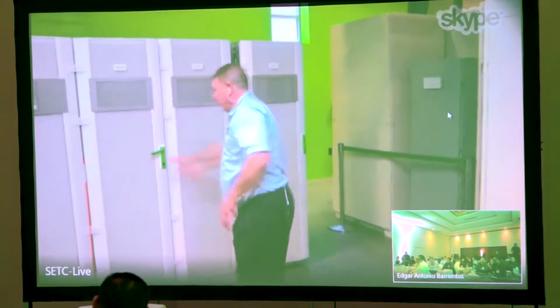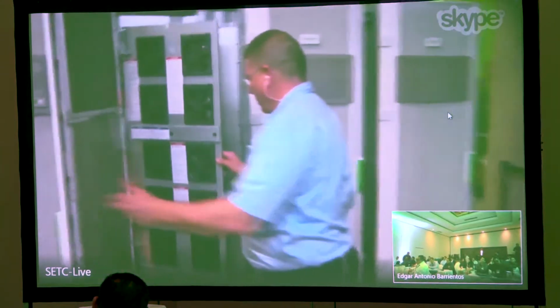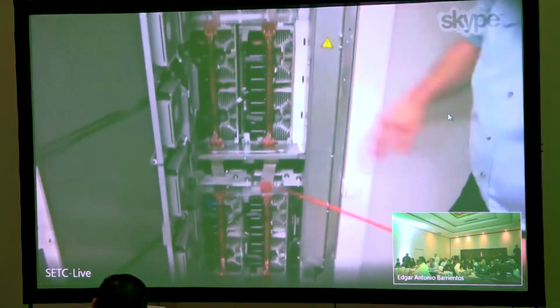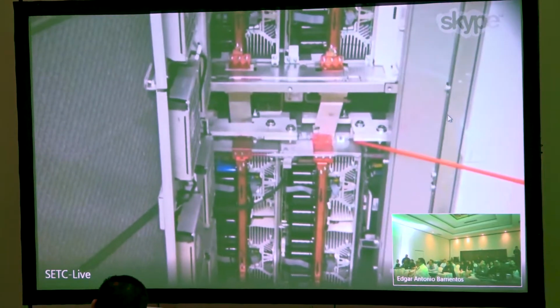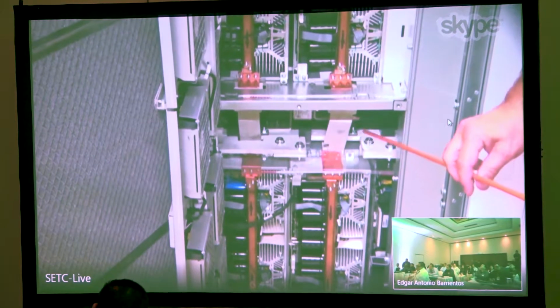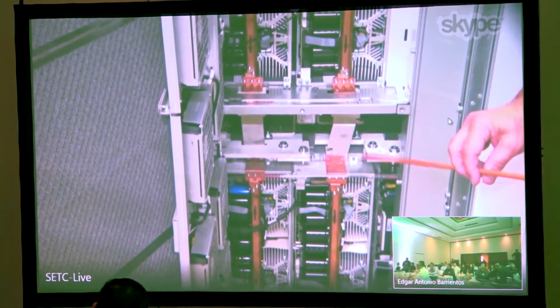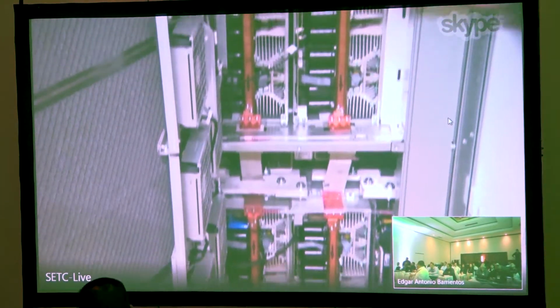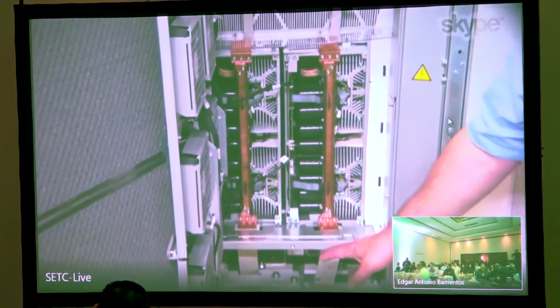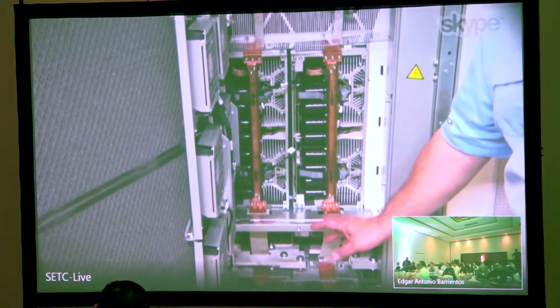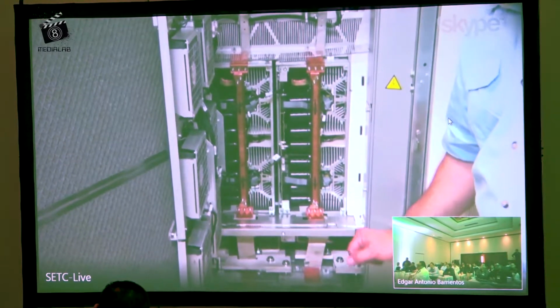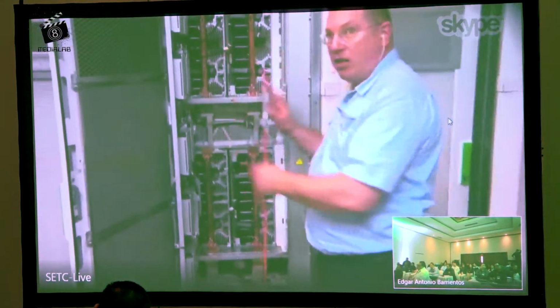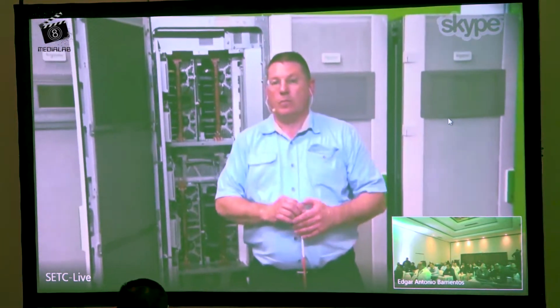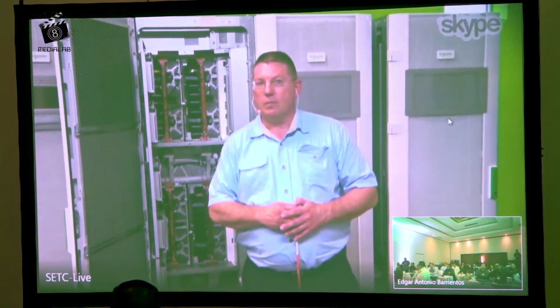Let's take a look at this again. At the very bottom here is bus bar that connects all the cabinets. And that bus is energized. As long as the UPS is on, that bus is energized. Okay? So in order to get access to one of these power blocks, we would be exposed to that, and from a safety perspective, we can't do that. So we have to de-energize the power cabinets and be on a maintenance bypass. Did I answer your question? Yes, thank you.